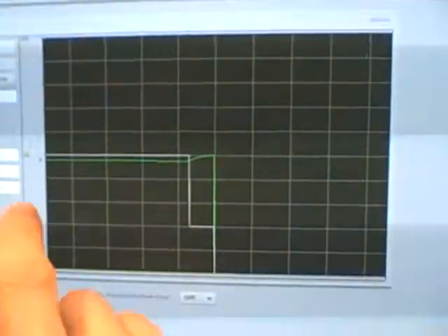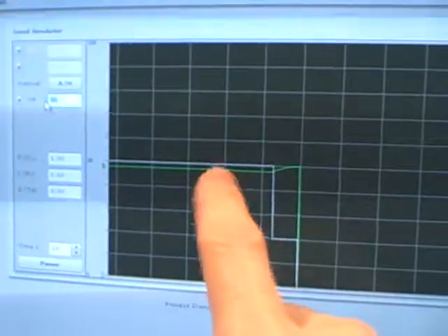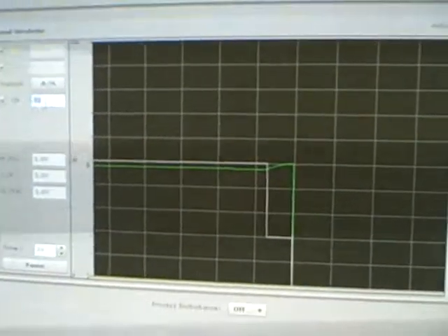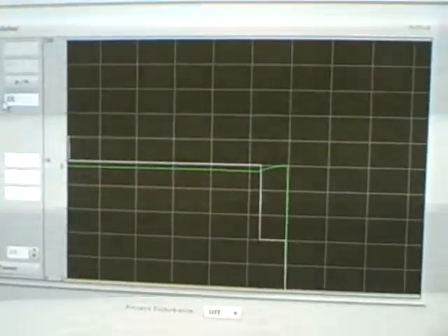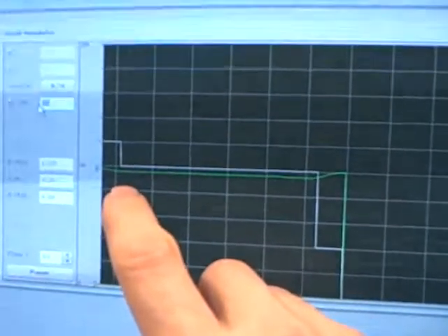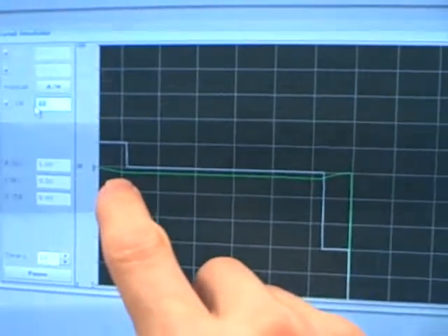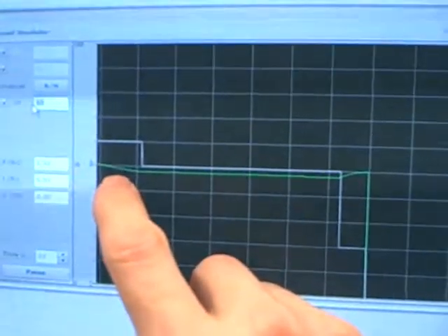Right now our valve is in manual mode, 50% open, and you can see how the process variable is pretty stable. We're going to do an output step change in manual mode, an open loop test, to see how the process responds. So I move the valve up to 60% open, and we're going to watch and see what the process variable does. We can see the process variable is rising. What's important to note is the way that it rises.